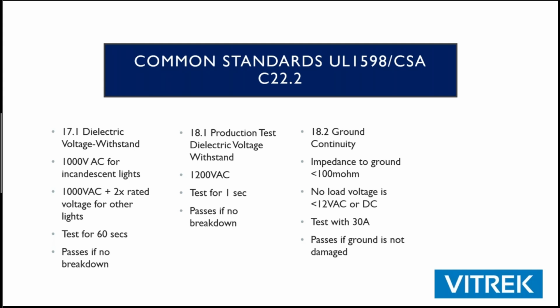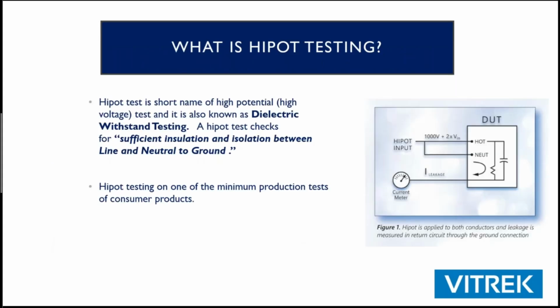Once again, you're going to see everything's very similar. They're going to specify ramp time, dwell times, leakage current, either in milliamps, or some of the standards will say the product should not break down. Especially in the V7X, we do have a setting that is breakdown only. We do not require the user to set a window of leakage current to pass a test.